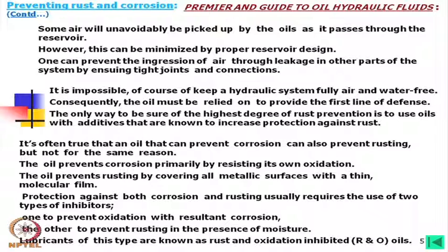Protection against both corrosion and rusting usually requires two types of inhibitors: one to prevent oxidation with resultant corrosion, and the other to prevent rusting in the presence of moisture. Lubricants of this type are known as rust and oxidation inhibitor oils, properly called R&O oil.